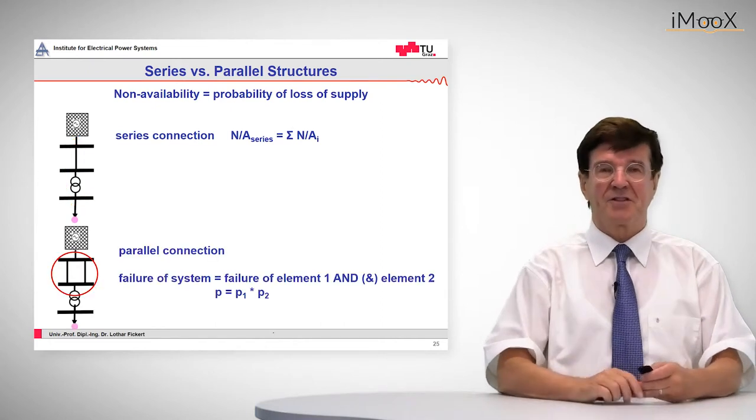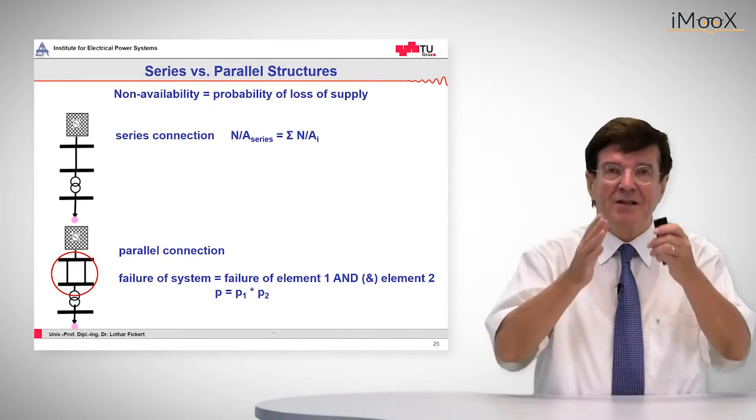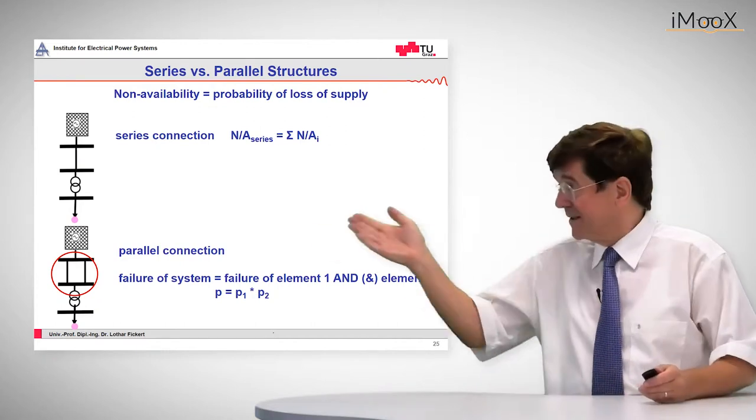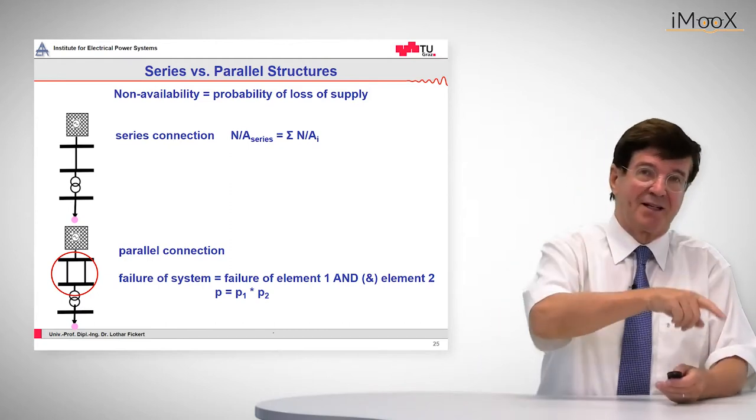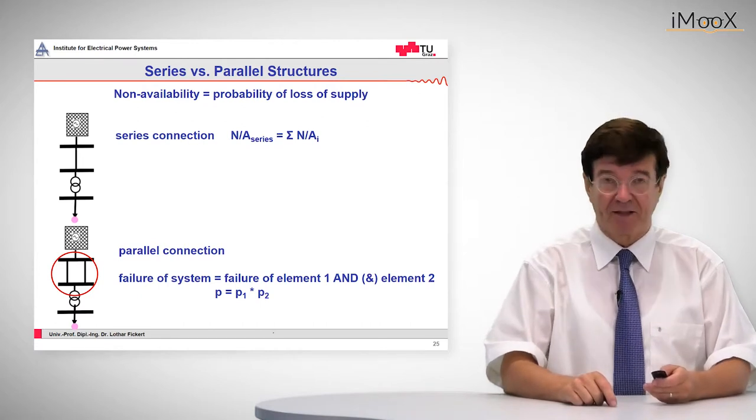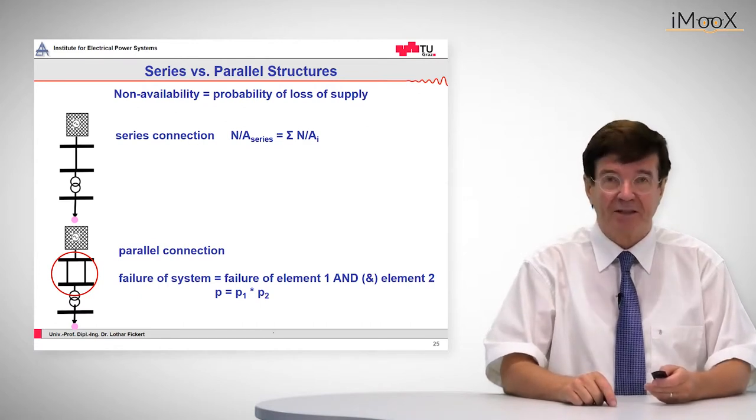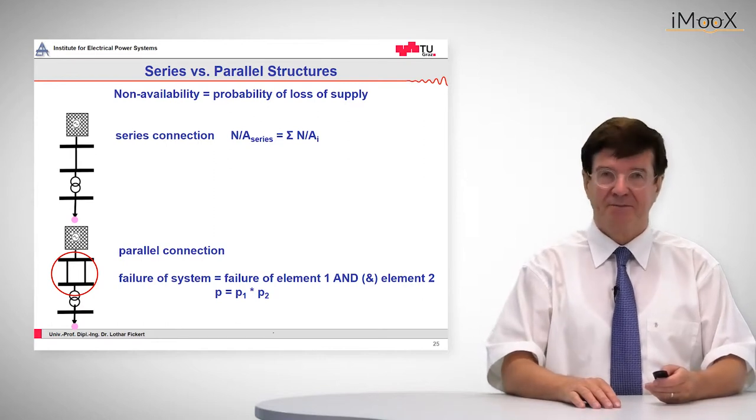In contrast, to apply the n minus 1 principle, we double lines as indicated here. The system now fails if both lines 1 and 2 fail. The product is the relevant quantity of the failure of these two parallel entities.